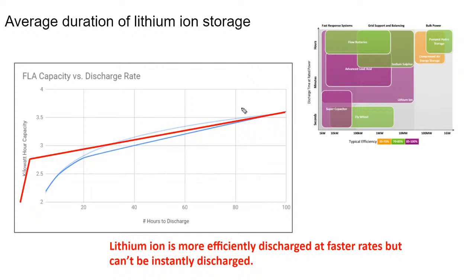What we're talking about is that even lithium ion has a kind of logarithmic decay curve of performance the faster it gets discharged. So a lot of lithium ion warranties are broken out to ask: are you cycling down to 80% and leaving a 20% reserve capacity, or doing a full 100% cycle, at which point you get different warranty values? That's a different way of saying don't discharge the whole battery so quickly. Stay at a slower pace of discharge and be easier on the battery so it lasts longer. Even top shelf lithium ion chemistries that are better than the Tesla Powerwall have this kind of go-gentle-on-the-battery-usage approach, giving better warranty shapes.